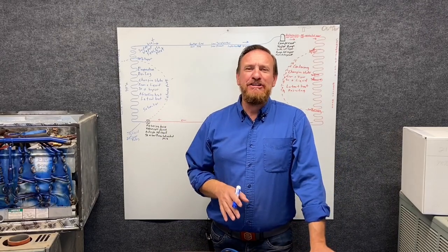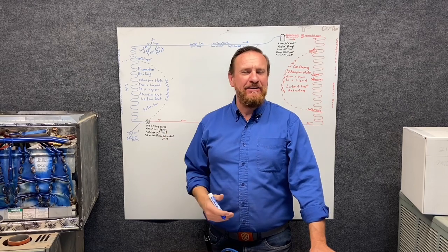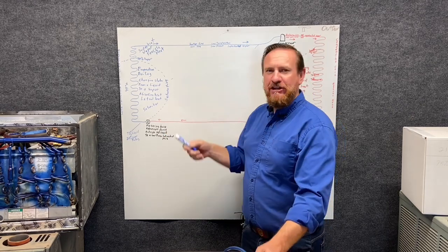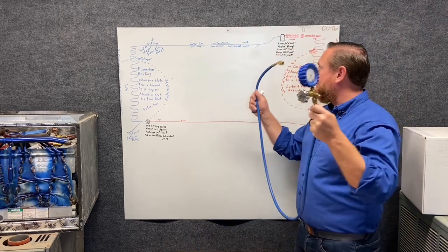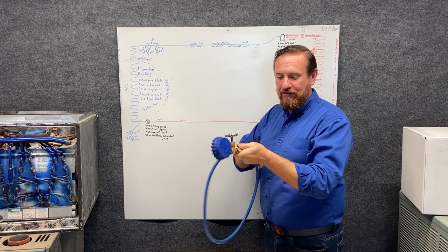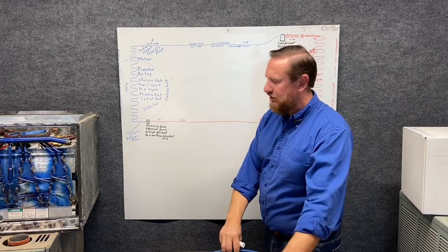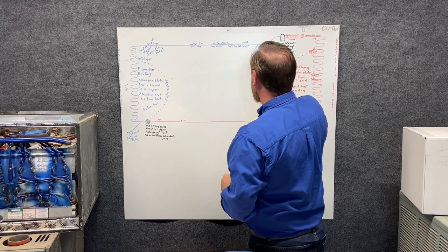Ideally, you have saturation down at this point, but we're just going to do a quick little review on it and then add our next component. Now, we know that saturation is PSIG converted to temperature. So when I have my pressure gauge and I hook it up to this suction line, we're going to get this PSIG, which is worthless, and convert it to a saturated temperature. So what I'm going to do is draw my little pressure gauge here, hooked to that line.